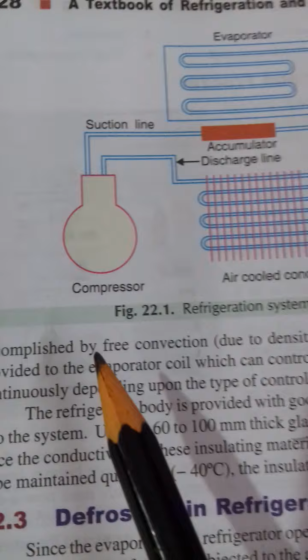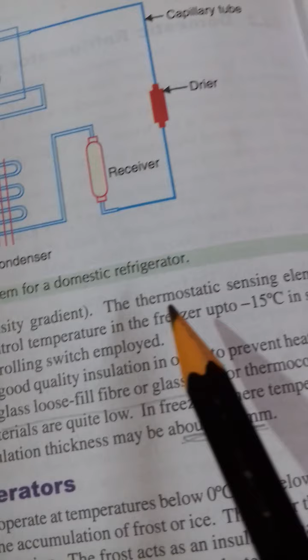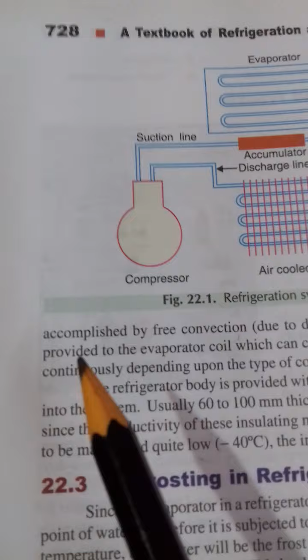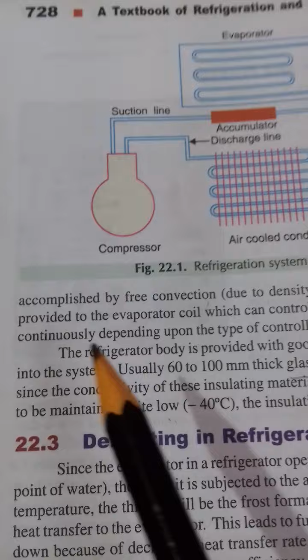The cooling of the lower space is accomplished by free convection due to density gradient. The thermostatic sensing element is provided to the evaporator coil, which can control the temperature in the freezer up to minus 15 degrees centigrade in steps or continuously, depending upon the type of controlling switch employed.